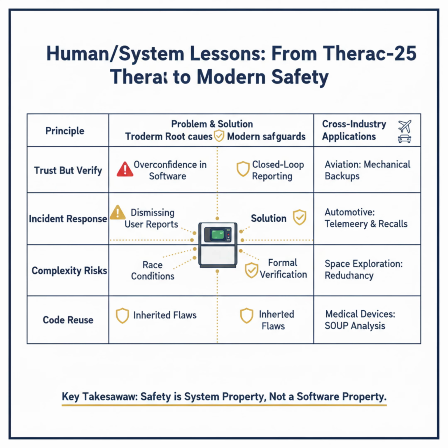4. Reuse requires revalidation. The Therac-25 software was adapted from earlier models, but the new machine's architecture was different. It lacked the hardware interlocks that had provided backup safety in the older designs. Reusing code in a new context requires validating that the safety assumptions still hold.